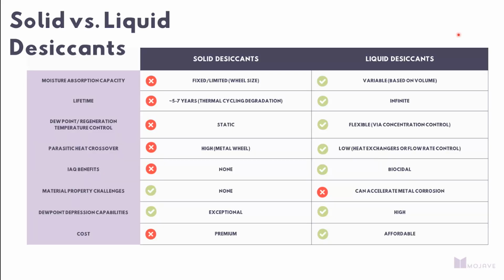A couple other things. There's no benefits around IAQ with solid desiccants. With liquid desiccants, they are naturally biocidal as covered previously. Material property challenges with solid desiccants, there's none. The only material handling challenge with liquid desiccants, which we've solved through the closed loop nature of our system, is that liquid desiccants are fundamentally a brine solution, and just like on a coastline, any sort of salty air or salty water, if they touch metal, do degrade it over time. From a dew point depression capability, solid desiccants have exceptional dew point depression capability and can hit negative dew points. Liquid desiccants can't hit quite the dew points that solid desiccants can, but they do have a really strong affinity for water and can still do some significant dehumidification.